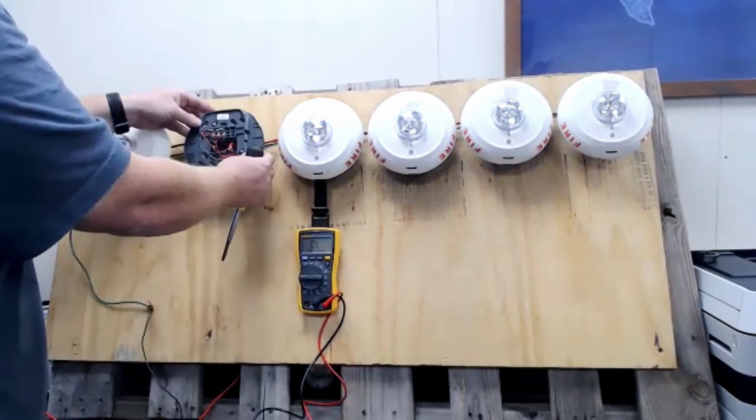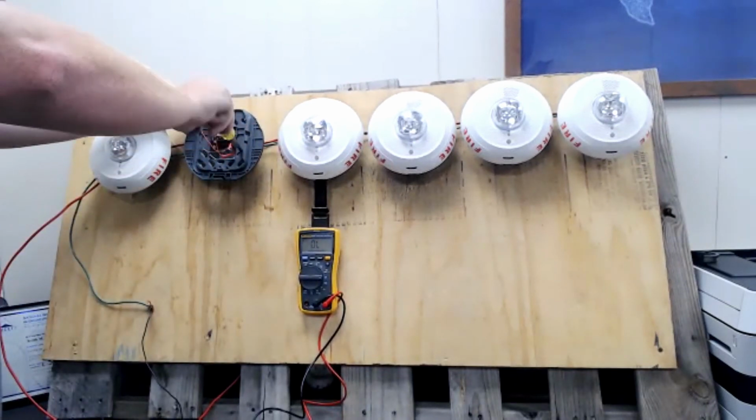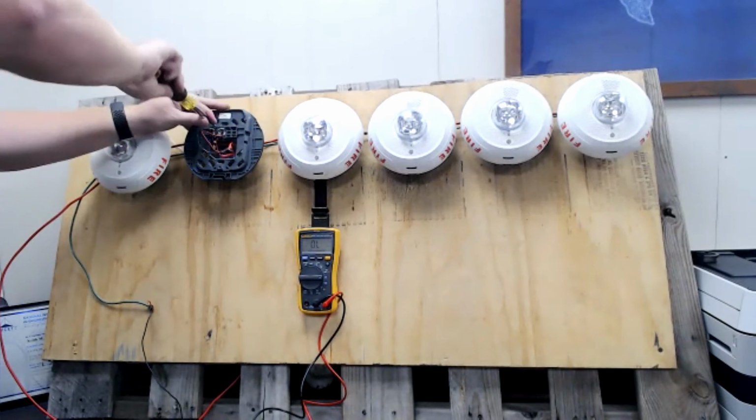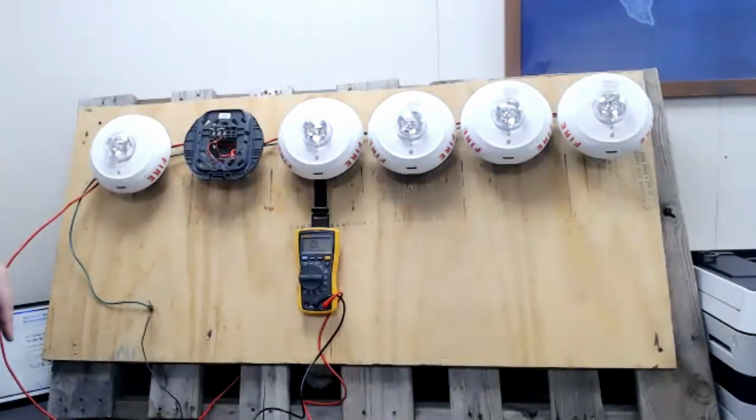And you can see how much extra wire was stripped. We don't need to be installing devices with this much extra wire stripped in there because it's just asking for ground faults. So, Mike, you should fire whoever trimmed this device.